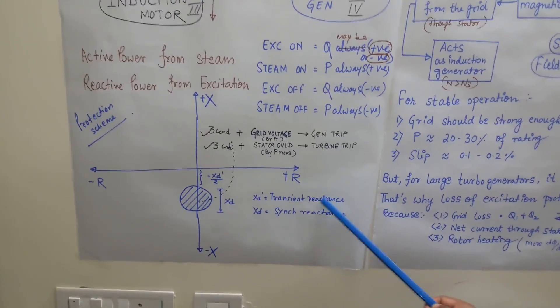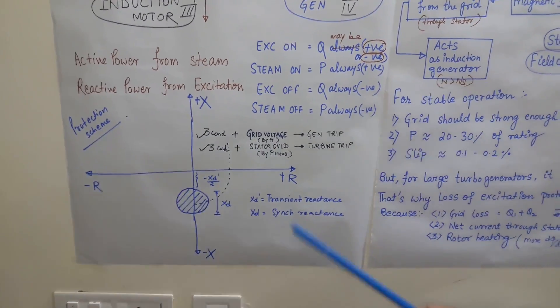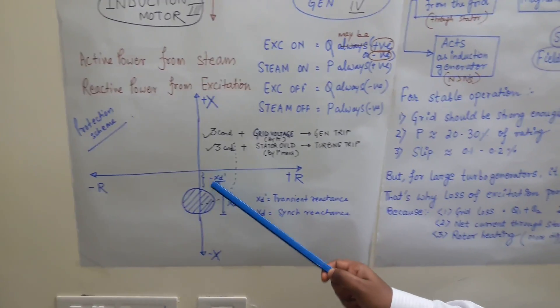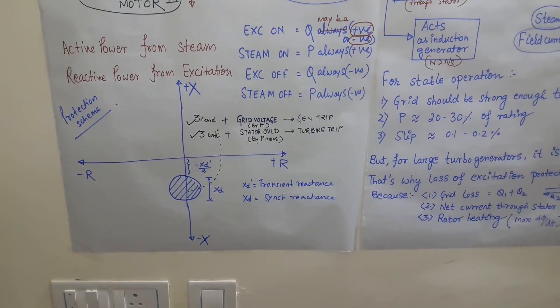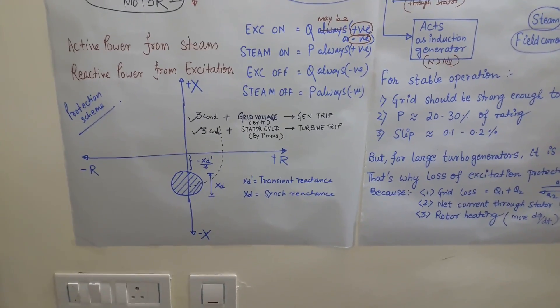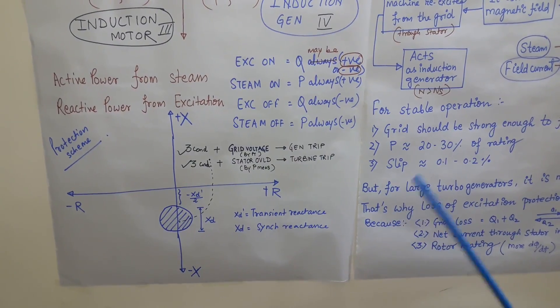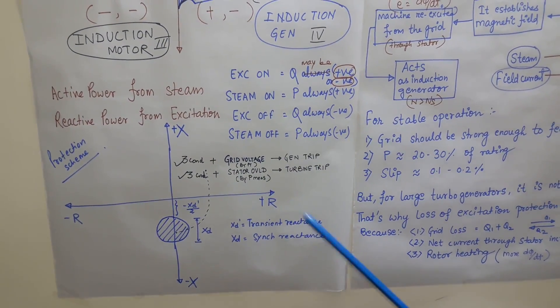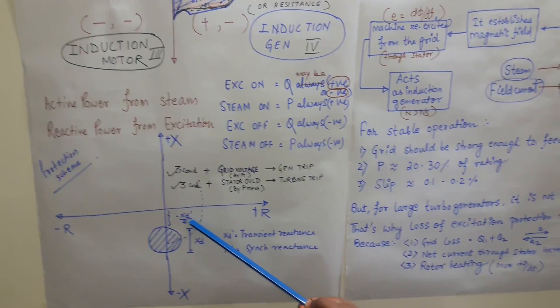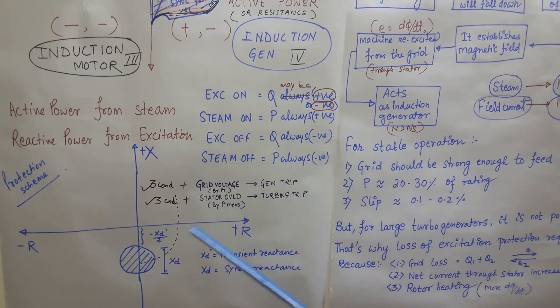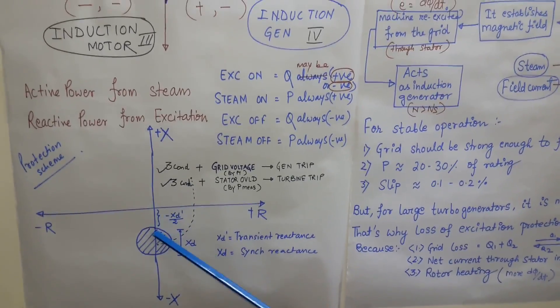Xd' is the transient reactance of the generator. The reason for taking this offset is that during the pole slipping condition of the generator at a load angle of 180 degrees, the impedance measured at the terminal of the generator comes out to be Xd' by 2. So we are taking this offset to avoid tripping during pole slipping of the generator.